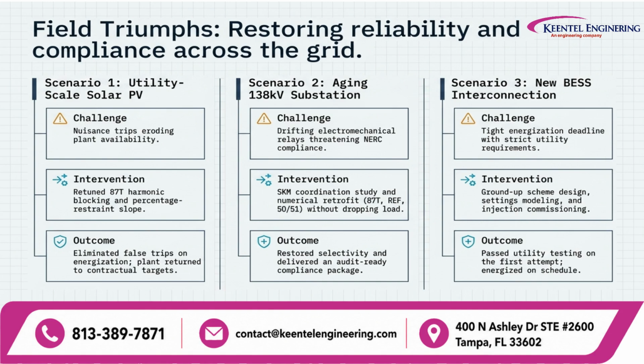The second scenario involves an aging 138 kilovolt substation. Here, drifting electromechanical relays were creating concerns about selectivity and NERC compliance. The intervention included an SKM coordination study and numerical relay retrofit involving functions such as 87T, REF, and 50/51. Importantly, the retrofit was performed without dropping the load. The outcome was restored selectivity and an audit-ready compliance package.